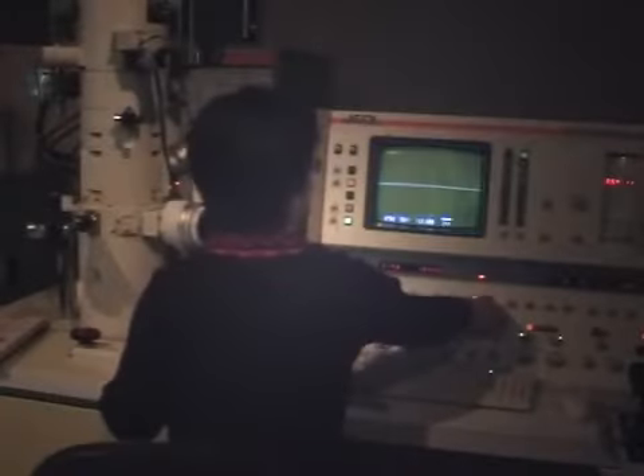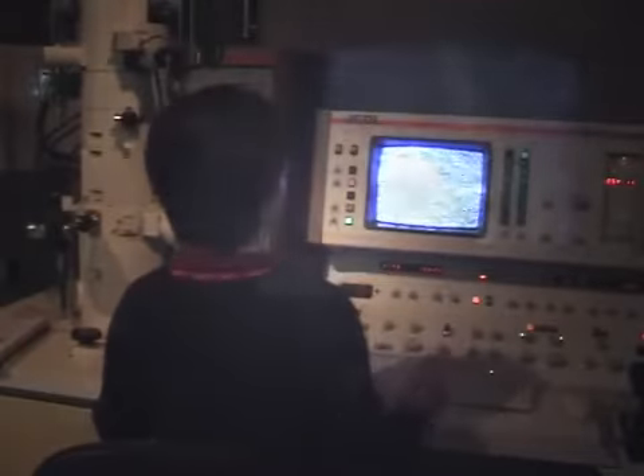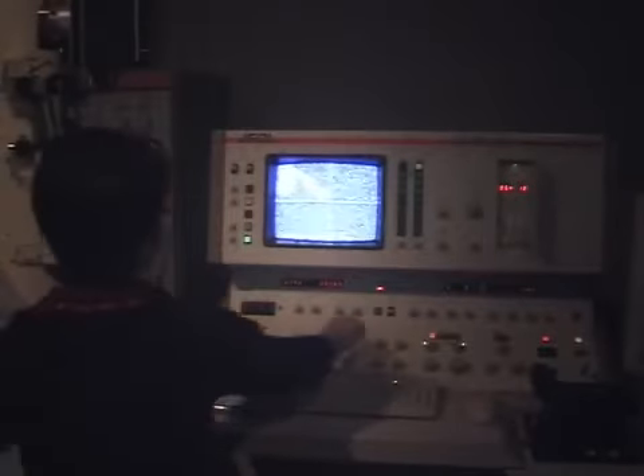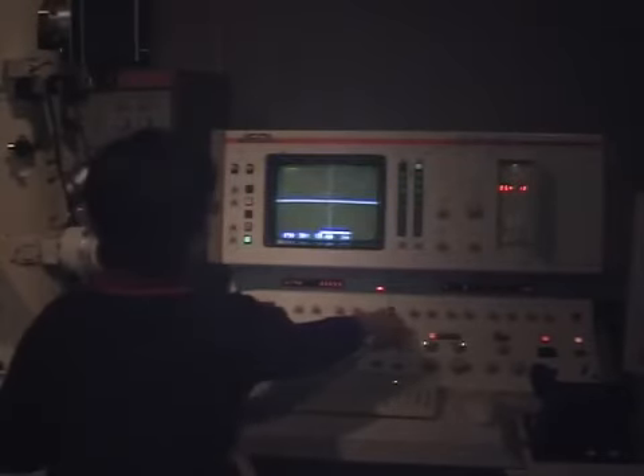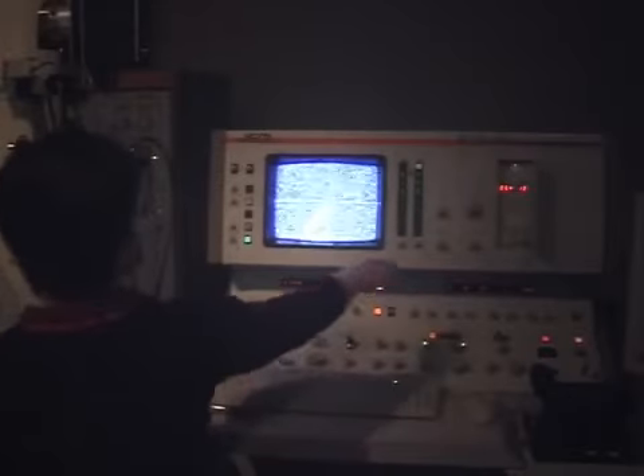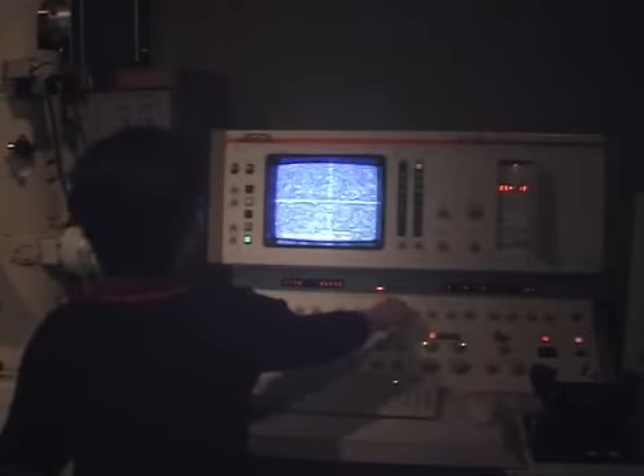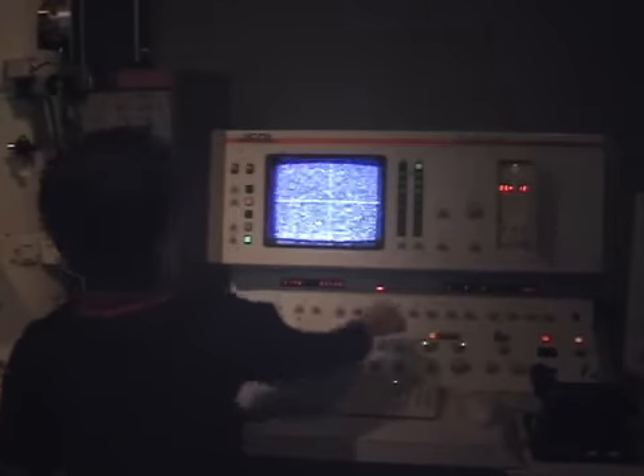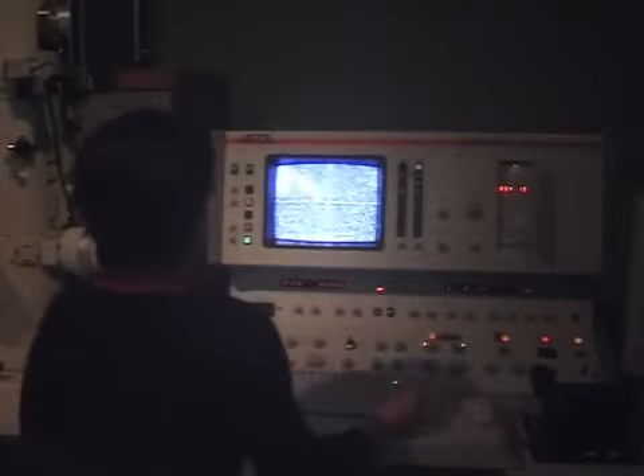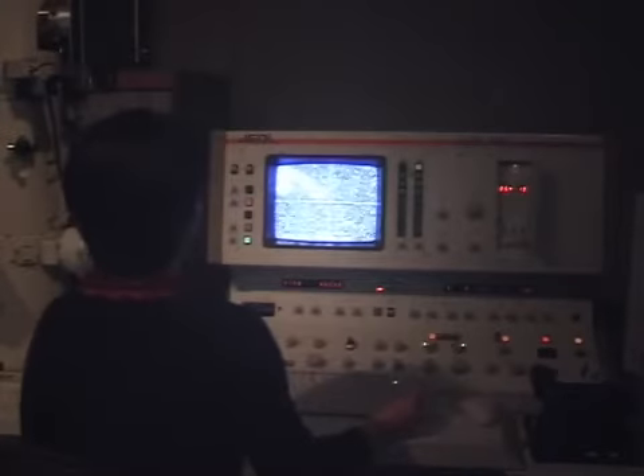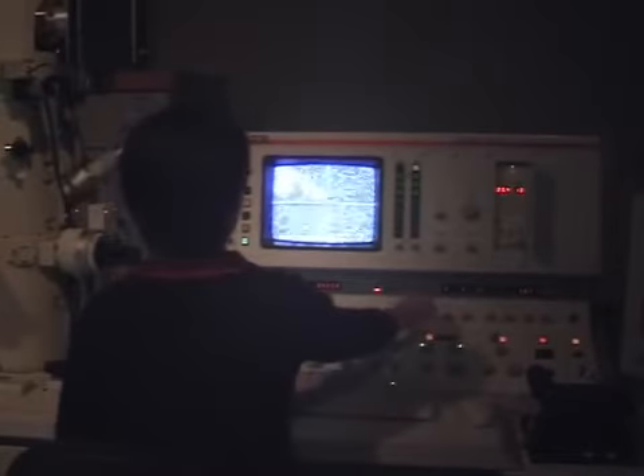Step up the magnification and repeat these steps. A good idea is to double the mag each time you repeat the alignment, and finish at a maximum magnification of about 25,000 times. This step is completed when points A or B move less than 1 micron from point O. Recheck the wobbler and use the CL tilt knobs to adjust if necessary.